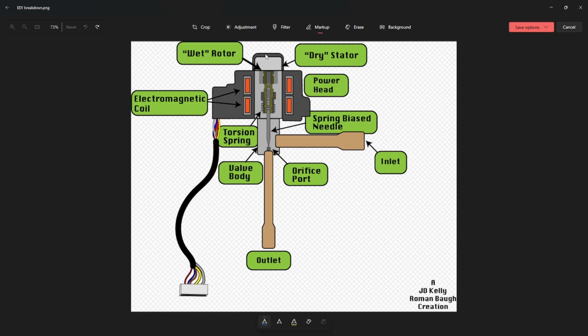So, with these stepper motors, the first test is literally just turn it off, turn it on again, and listen. On startup, you will hear a ticking noise. It sounds like this. Tick, tick, tick, tick. That is a normally functioning EEV. It's driving itself closed, driving itself back open, and making sure it has a reference point for when it needs to start adjusting that valve.